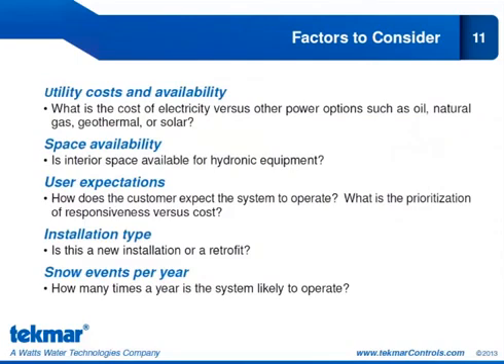Factors to consider when choosing between electric and hydronic include utility cost and availability of other power options — compare the cost of electricity to oil, natural gas, geothermal, or solar. You also need to consider space availability for hydronic equipment, user expectations around responsiveness versus cost, and whether it's a new installation or a retrofit, since electric cables are easier to retrofit. Finally, consider how many snow events per year your area sees — the more often the system operates, the more worthwhile cheaper fuel options become.